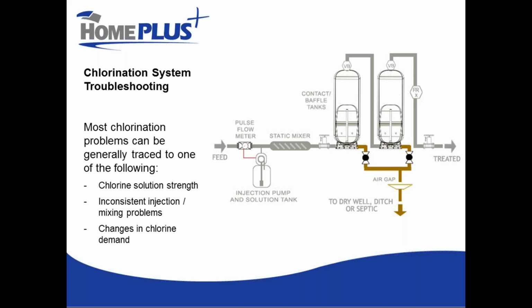So if the amount of iron or organic matter was to increase, we would have more chlorine demand. And unless we increased the amount of chlorine we were injecting, we would have less residual coming out the other end. Chlorine also dissipates over time. So the strength of our chlorine solution that we're injecting is not a constant. When you mix up a nice batch of chlorine today, and you come back a month from now, if you still have chlorine in your solution tank a month from now, it will not quite be as strong as what you started with. You come back in 6 months and it will be about half as strong.